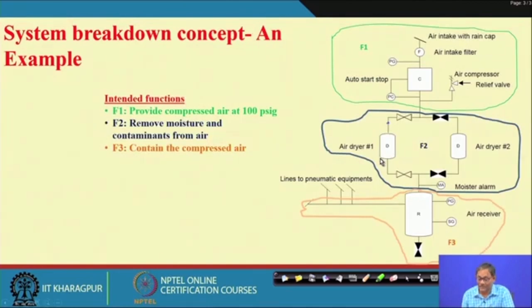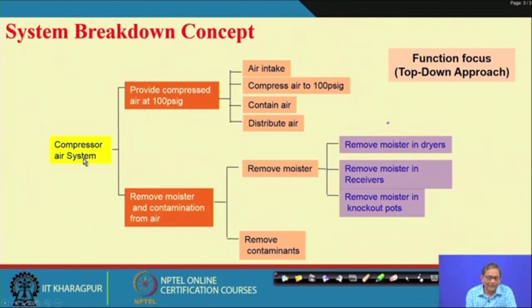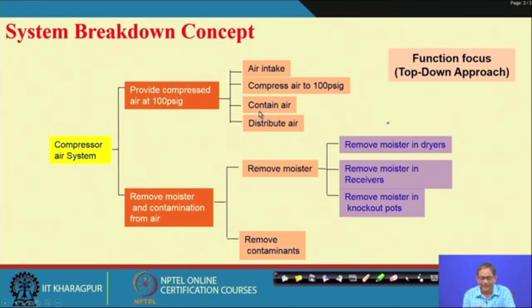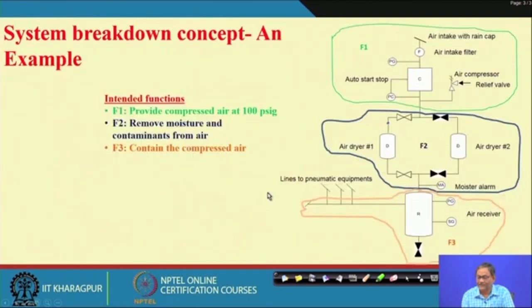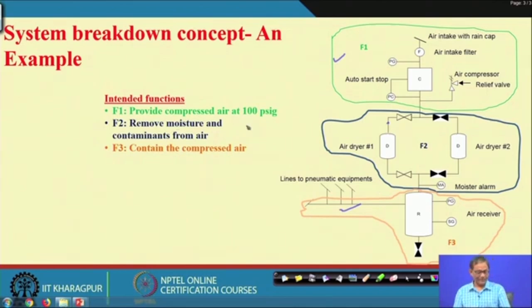With reference to this, the functional breakdown — you see the compressed air system: what is the purpose of this compressor system? Provide compressed air at 100 PSIG, remove moisture and contamination from air — these are the two things to be done. When we talk about providing compressed air, these are the sub-functions: intake air, compress air, contain air, distribute air.